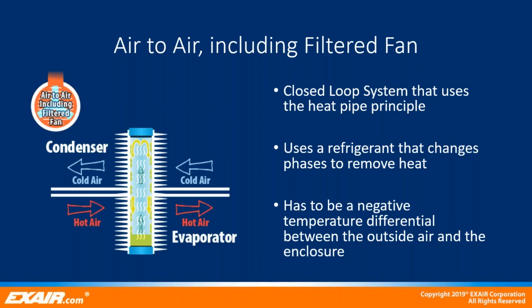In layman's terms, air-to-air heat exchangers cannot cool the enclosure lower than the ambient air temp. So the ambient temperature needs to be controlled. And circulation fans are a wear item that can lead to a premature failure or cabinet overheating.